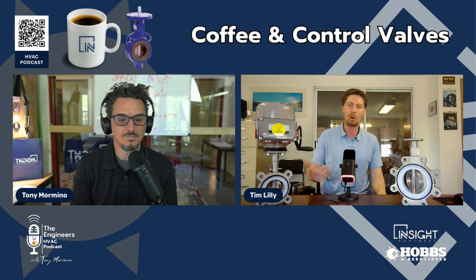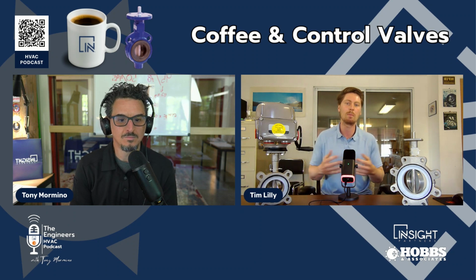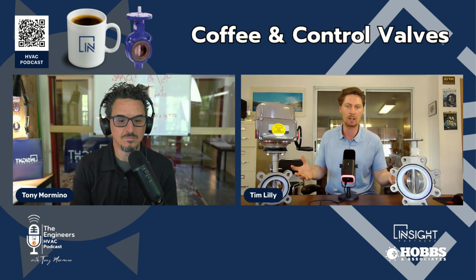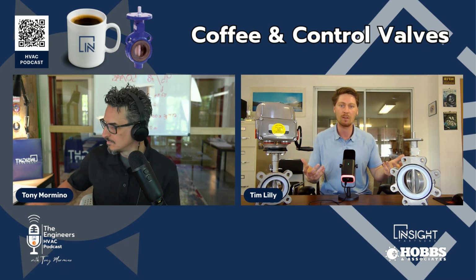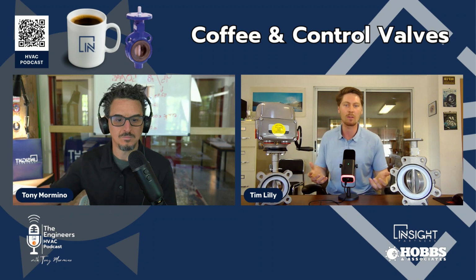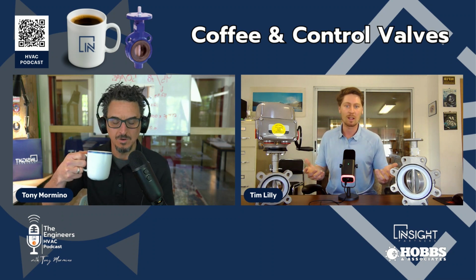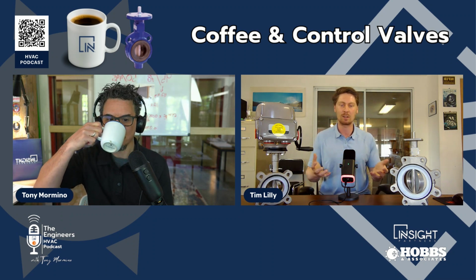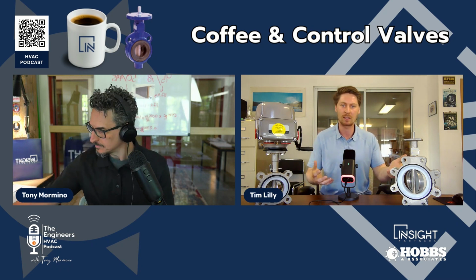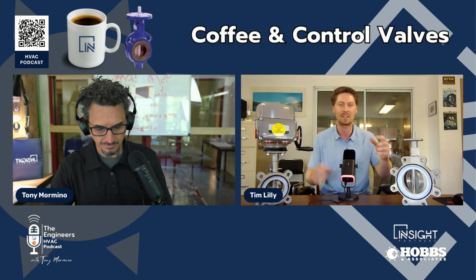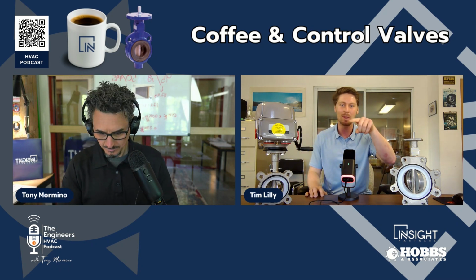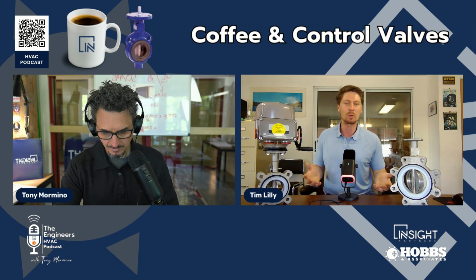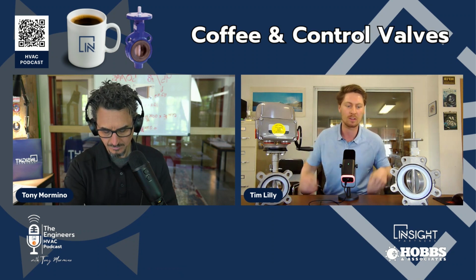And so to answer your question, there are really three main types of valves when you get into these larger, let's say, control applications. You have what's called a butterfly valve, a characterized ball valve, and a globe valve. And when you design a system and you go get a control valve, let's say the spec just calls for a control valve, it's that little icon with the hat on the top. What you want is what's called equal percent flow characteristics.